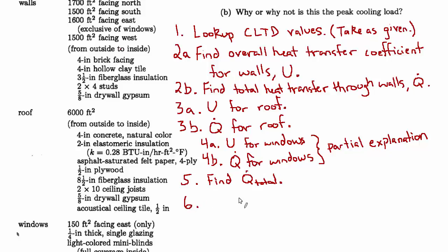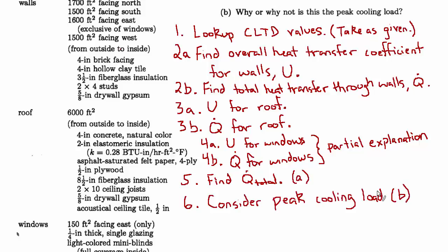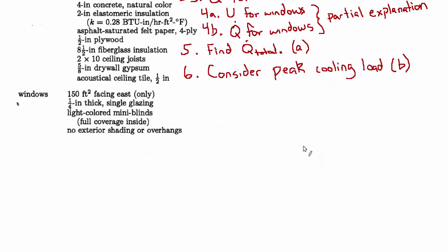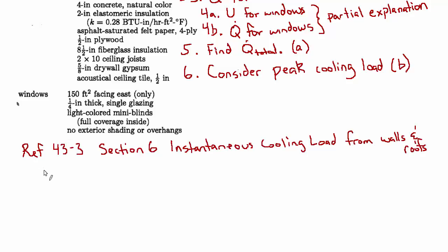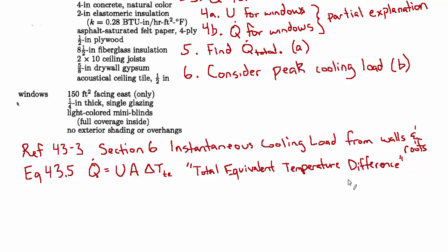Lastly, we'll give thought to part B — why or why not is this the peak cooling load. For background, start with section 43.3 of the MERM on instantaneous cooling load from walls and roofs. The governing equation is 43-5: total heat transfer Q-dot equals the overall heat transfer coefficient times area times delta-T sub TE, the total equivalent temperature difference. This method determines the instantaneous heat gain. Delta-T sub TE depends on construction type, geographical location, time of day, and wall orientation — read from extensive tabulations.